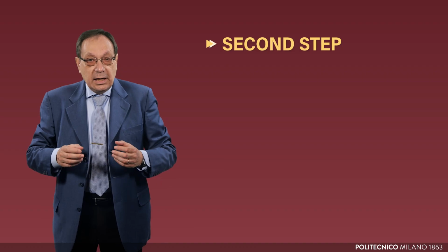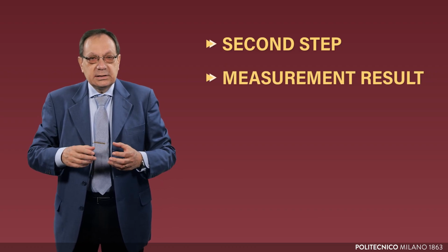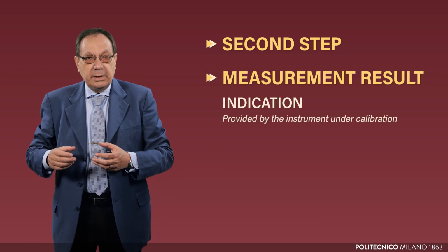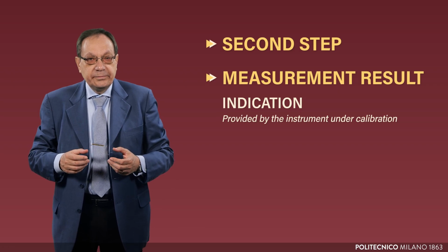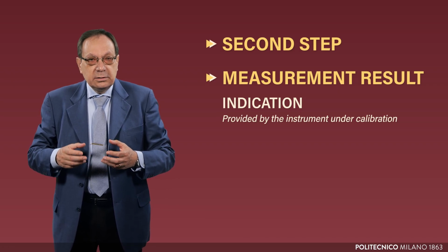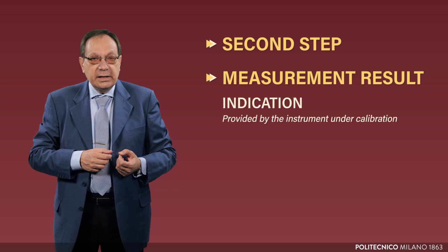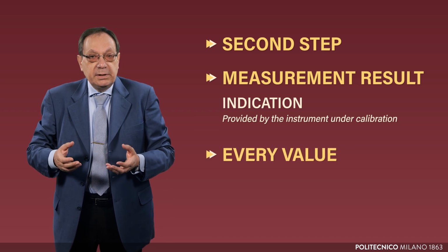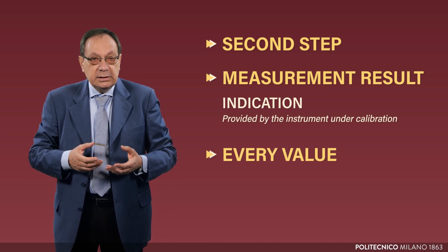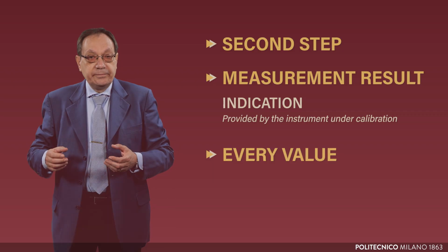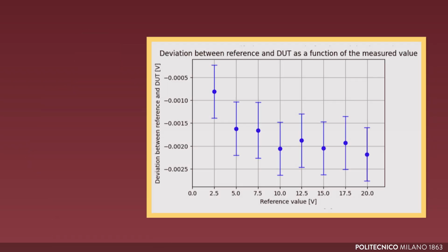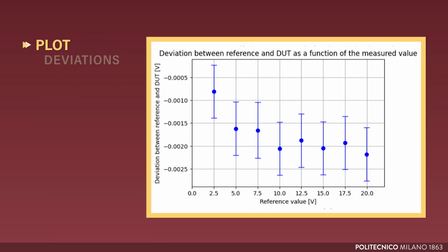We now need to address the second step, that is, how to obtain a measurement result starting from the reading provided by the instrument under calibration. And this applies not only to the values considered in the first phase, but to every value that can be measured by the calibrated instrument within that measurement range. To do this, it is useful to plot on a graph the deviations between the value measured by the instrument under calibration and those measured by the reference instrument.